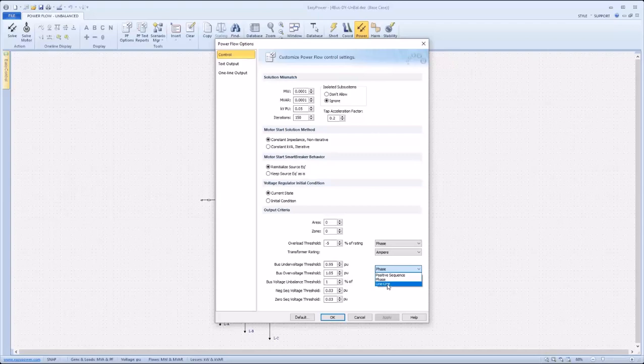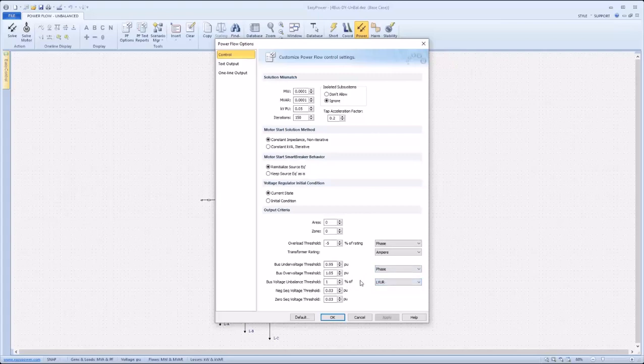Line-to-line uses, as the name suggests, line-to-line quantities to compare to the threshold specified. In addition, there's a bus voltage unbalance threshold with standard calculation options to compare phases for unbalance, and finally, negative sequence and zero sequence voltage thresholds for comparison.